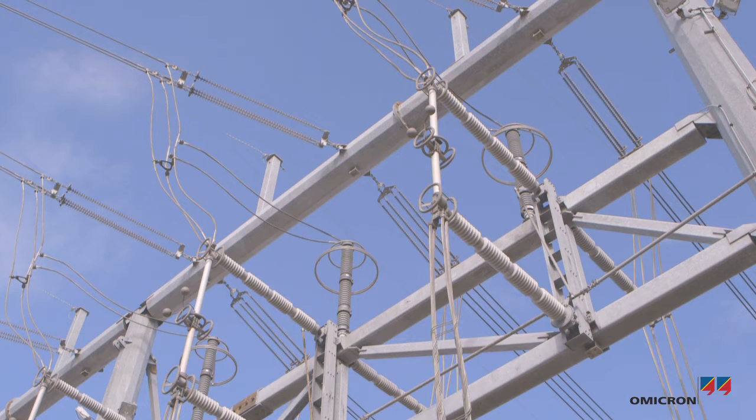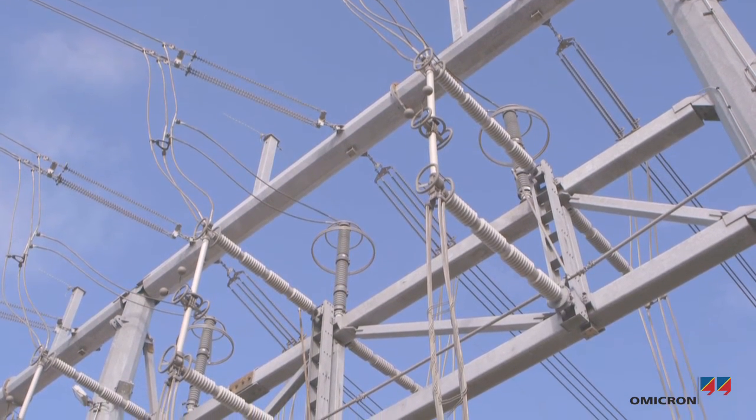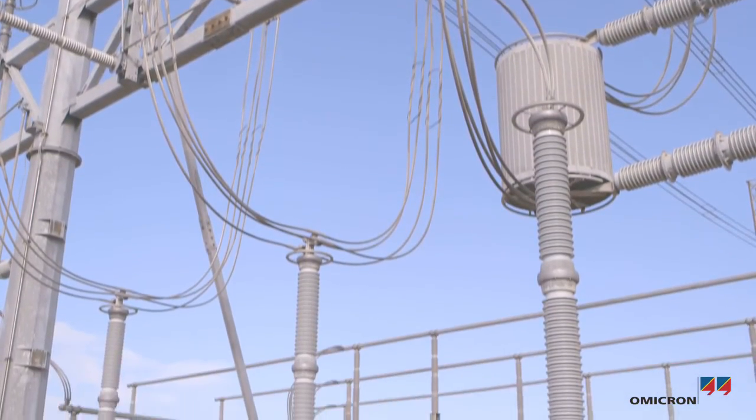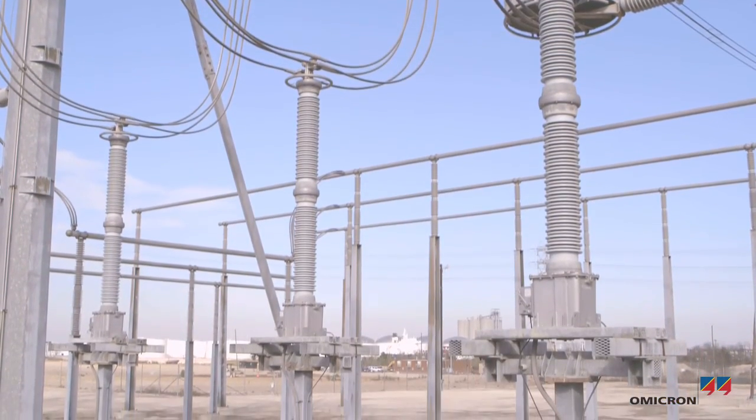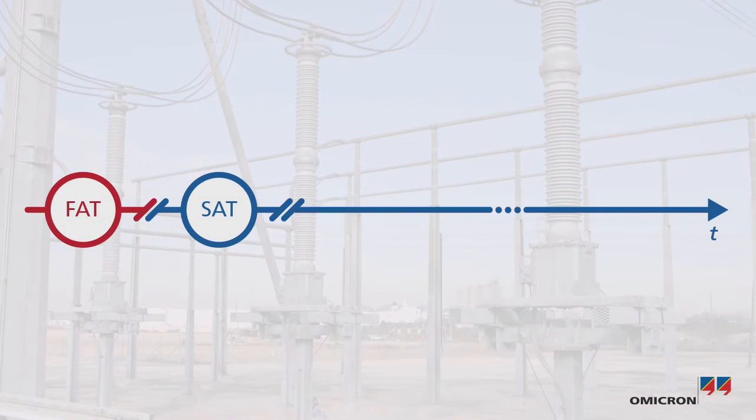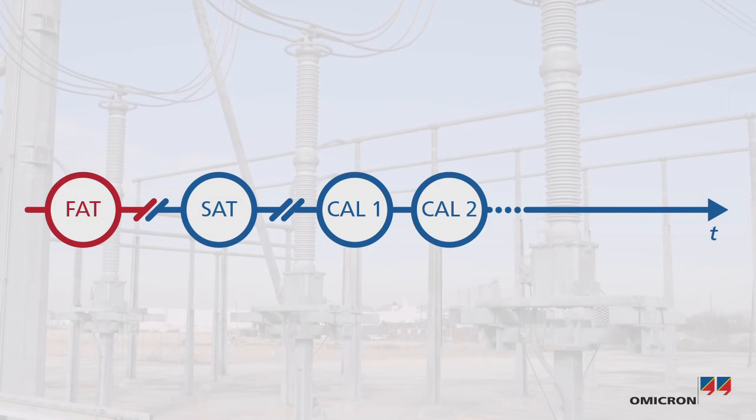In order for a protection system to function reliably and to have correct revenue metering, voltage transformers must operate within their specified accuracy ratings. They should be calibrated on a routine basis in order to ensure their reliability throughout their lifespan.